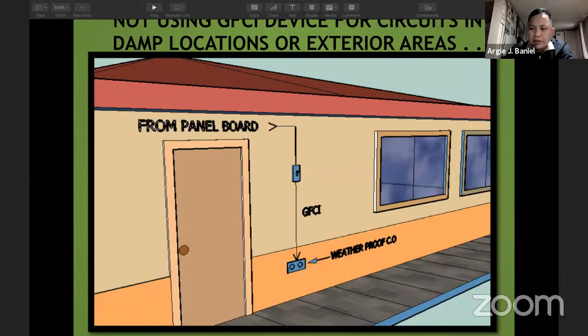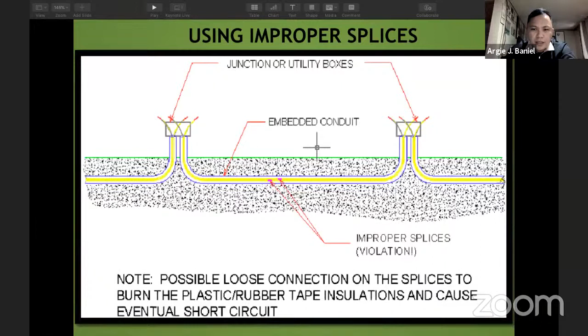So not using a GFCI device for circuits in damp locations or exterior areas. So junctions or utility boxes, embedded conduits. Improper splices are a violation. Possible loose connection in the splices can burn the plastic rubber tape insulation and cause an eventual short circuit, especially when outdoors, since sometimes our friends the ants and animals get inside. So these are improper splices between the junction boxes.